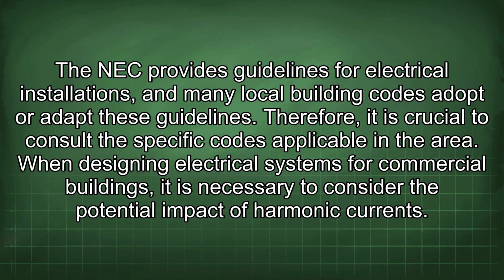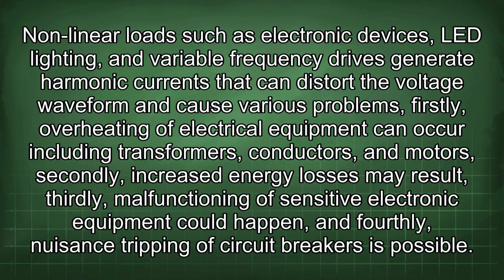When designing electrical systems for commercial buildings, it is necessary to consider the potential impact of harmonic currents. Nonlinear loads such as electronic devices, LED lighting, and variable frequency drives generate harmonic currents that can distort the voltage waveform and cause various problems. Firstly, overheating of electrical equipment can occur, including transformers, conductors, and motors. Secondly, increased energy losses may result. Thirdly, malfunctioning of sensitive electronic equipment could happen. And fourthly, nuisance tripping of circuit breakers is possible.